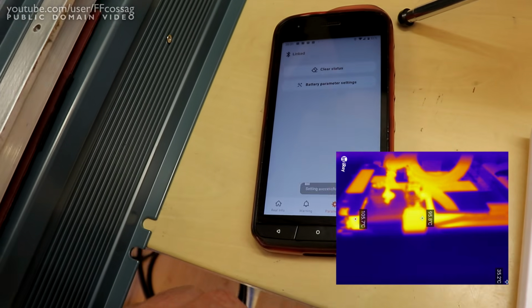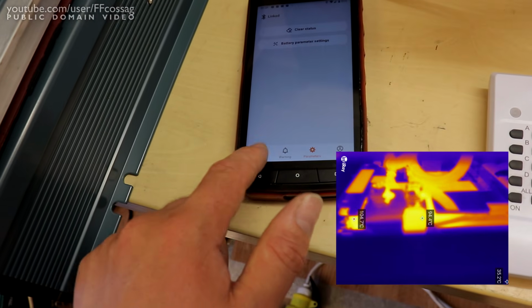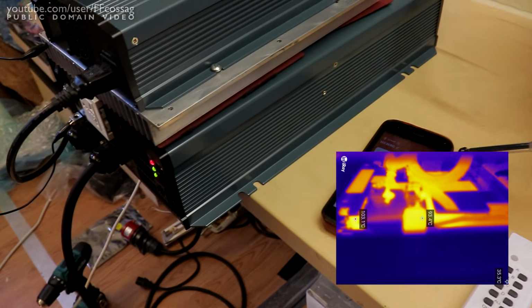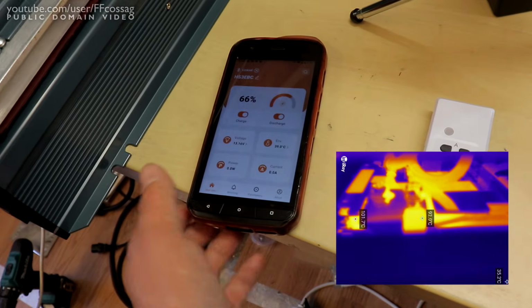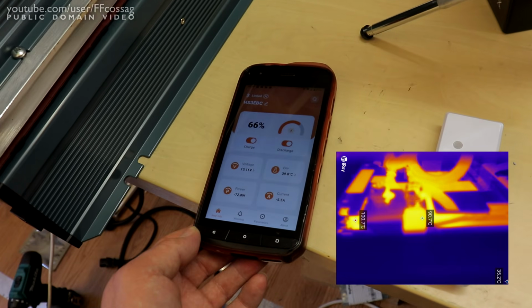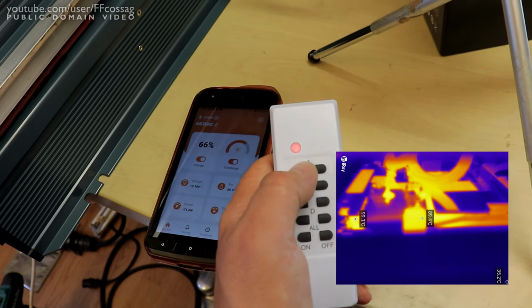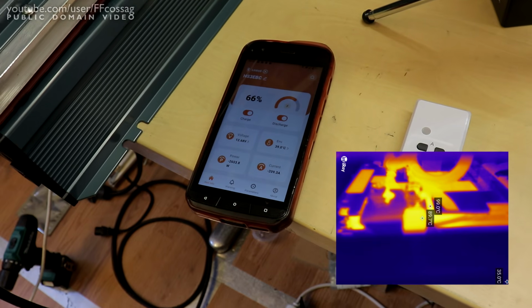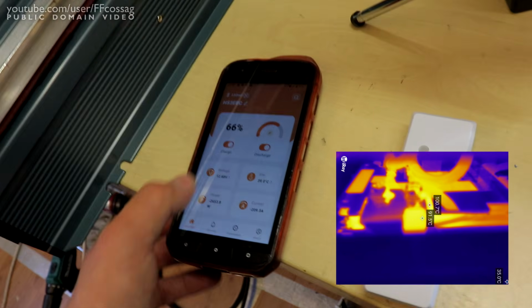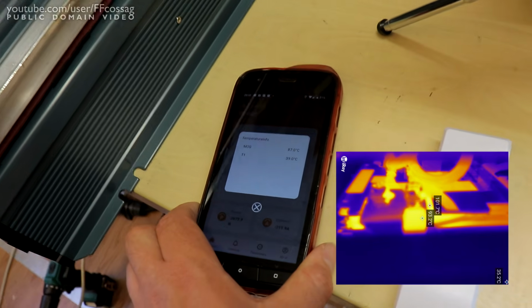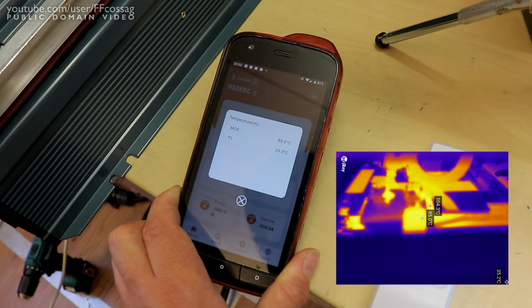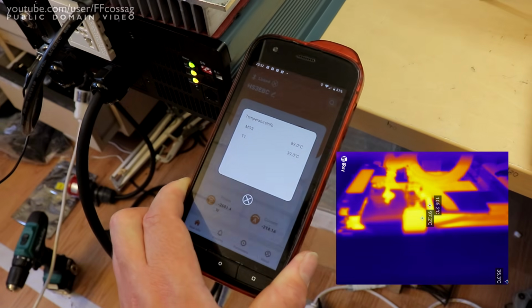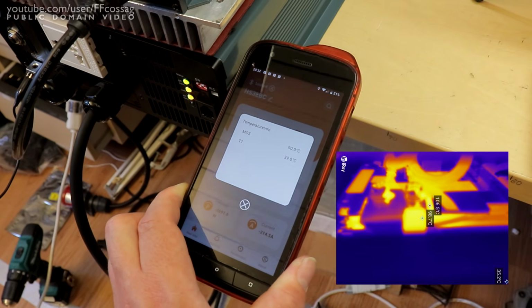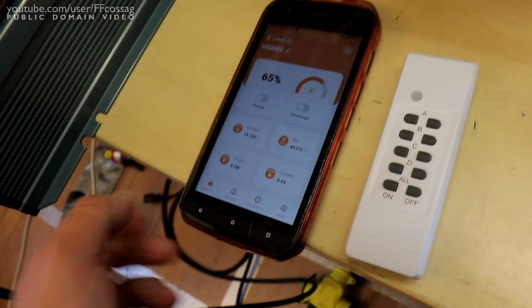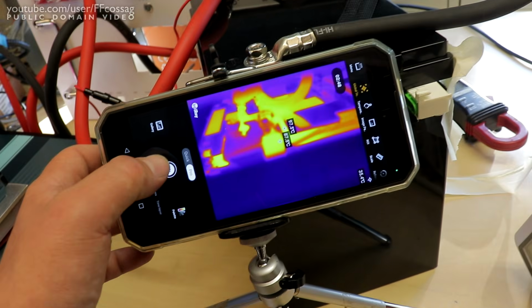So can we do clear status, confirm? It's turned back on. So the inverter is going to start again, trying to draw 200 amps. So we'll just immediately reset with a 200 amp load. And this is just going to trip super fast now. It's so heat soaked. 88, 89, and 90. It's going to trip. Yeah, you know what? I'm not concerned.